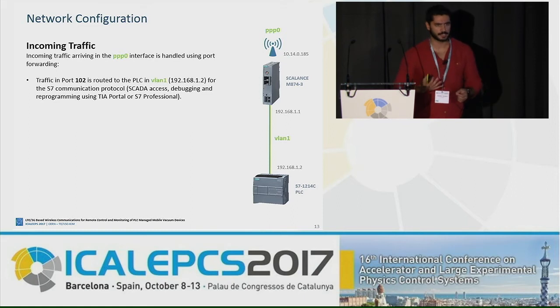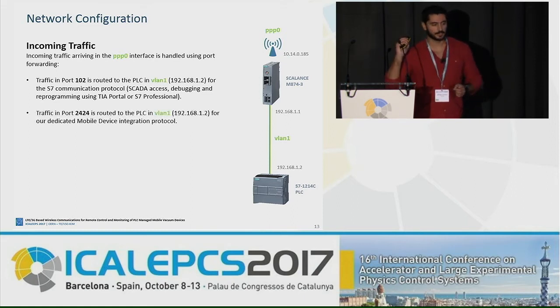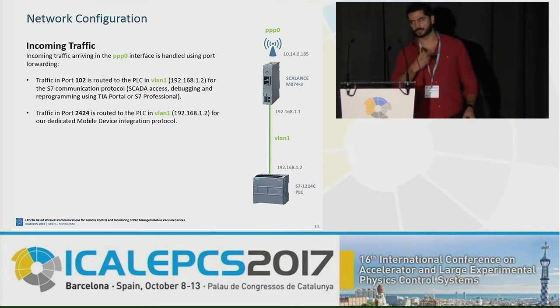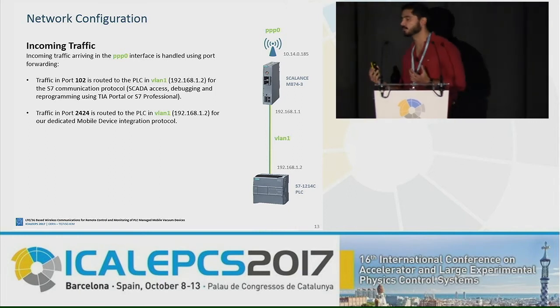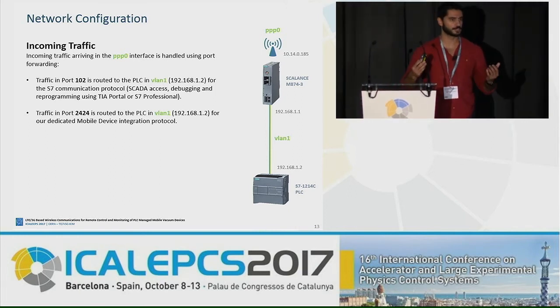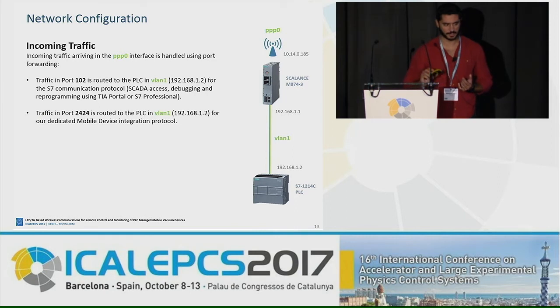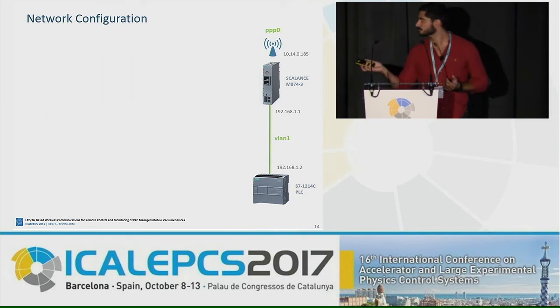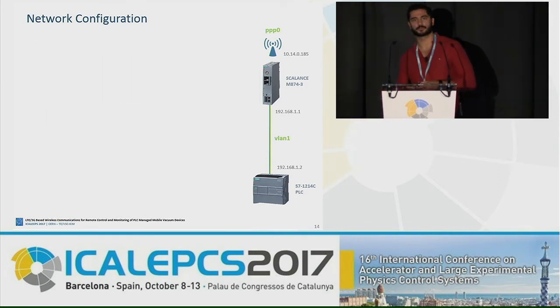We can make a SCADA connection, a connection for programming or diagnostics, and we also route port 2424, which is the port we chose to implement our own mobile communication protocol for integrating these devices into the control system. So the PLC is reachable on the ports we need using the IP of the SIM card.